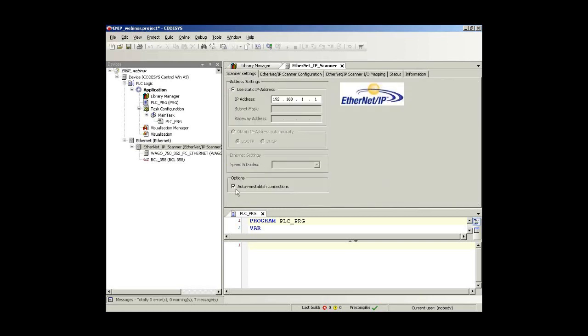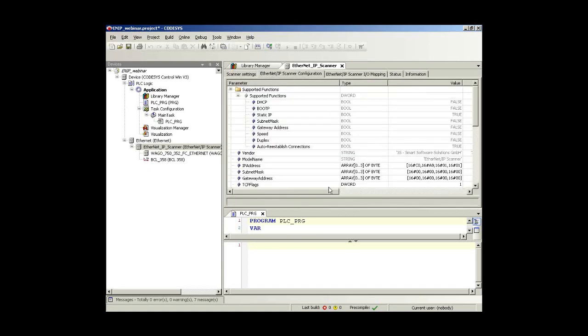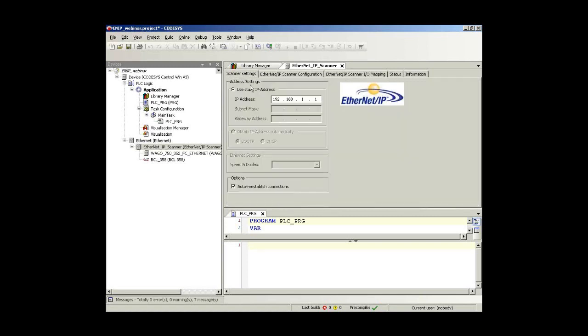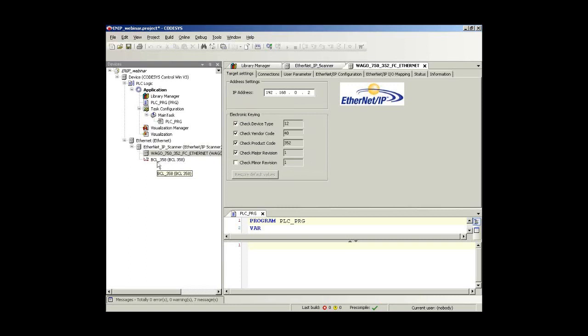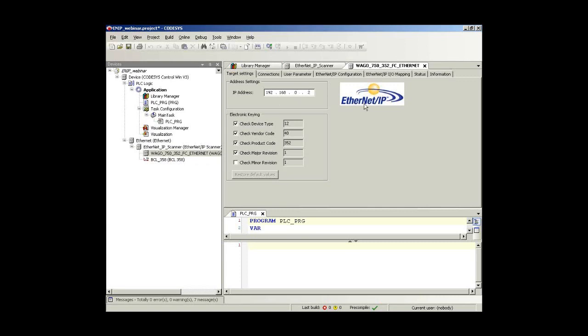Now of course I need to configure the scanner and to give him the IP address which I am physically using for my EtherNet/IP connection. In this case, I know that this adapter has this IP address 192.168.1.1. There are some more register cards here in that scanner. But in fact, this is almost everything you need to configure. There is one option. You can tell the scanner that it should auto-establish connection after there was a connection break.